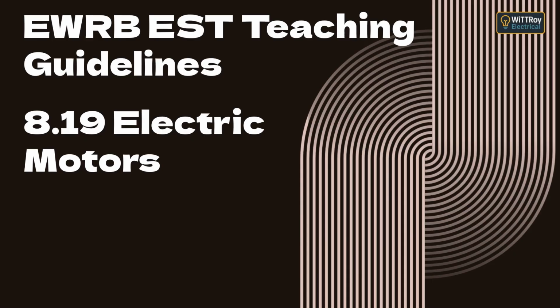Bringing it all together. Let's summarize Topic 8.19, Electric Motors Part 2. We began with the principle of 3-phase induction motors, how the rotating magnetic field induces current in the rotor to produce torque. We learned how slip allows rotation, and how starting methods like DOL, star delta, and soft starters reduce current surges. We looked at reversing direction by swapping two phases and controlling speed using VSDs. We studied overload, short circuit, and earth fault protection under AS/NZS 3000. Finally, we covered motor fault finding and finished with a real example of diagnosing a faulty three-phase motor.